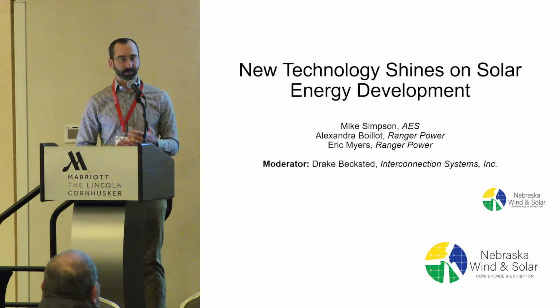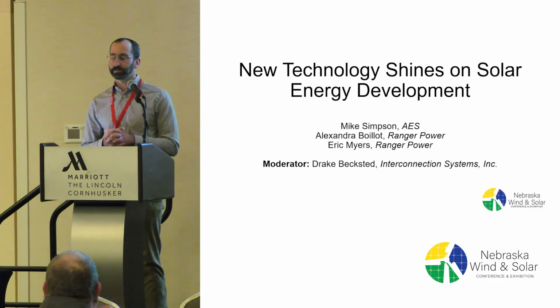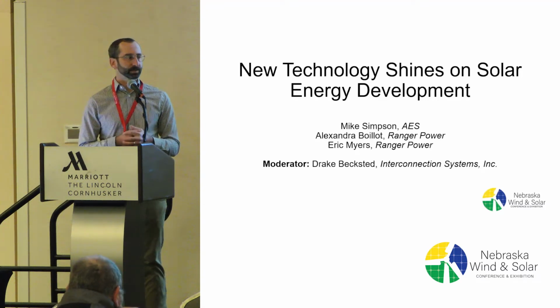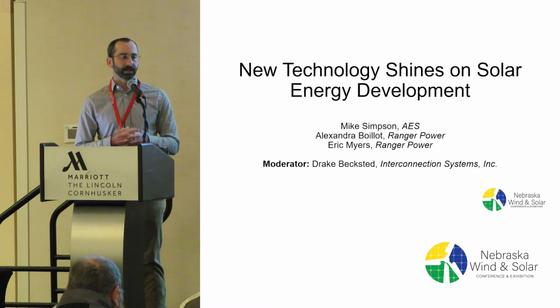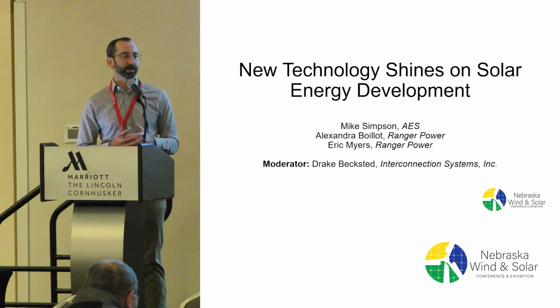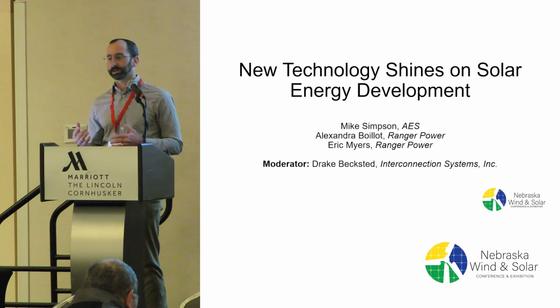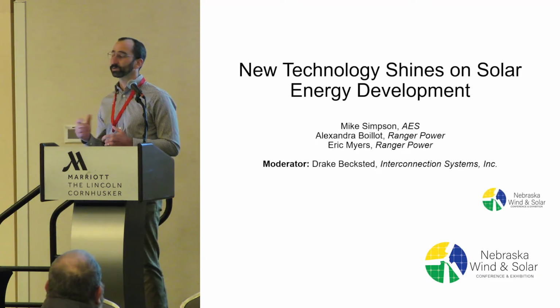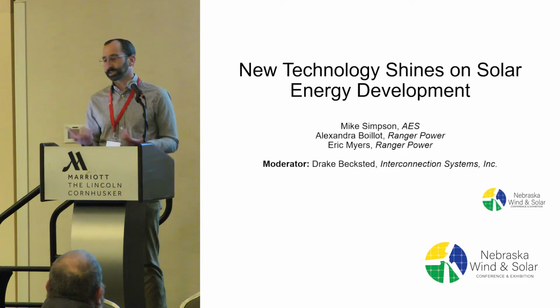We're seeing this in a couple of niche areas, right? We've got about 5 years of operating history on solar and storage, and we've been both DC coupled and AC coupled. Some of the early projects that we had done out in Hawaii, where there are a little bit more unique cases when it comes to grid integration, have shown that using the ability to take these inverter-based resources and actually control the entire grid with them is something that's quite feasible.